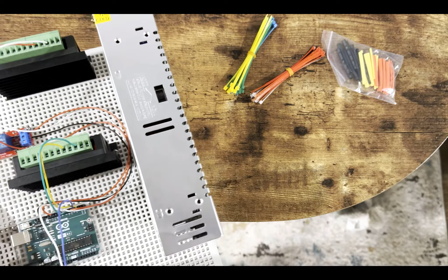So like clockwork, we can see that the back plate to his electronics enclosure is nylon. Yes, it appears it's very easy to mount everything as it's removable, but once again, as discussed, it's non-conductive, so he will use a ground bus or a metal plate. If he uses a ground bus, he can just terminalize everything right off the ground bus. If he uses a metal plate, everything would screw to the metal plate naturally, and then it would be grounded, pending he uses a terminal splitter, which is metal, that has a ground lead coming from his power supply's ground run to it, therefore conductively grounding the back plate.